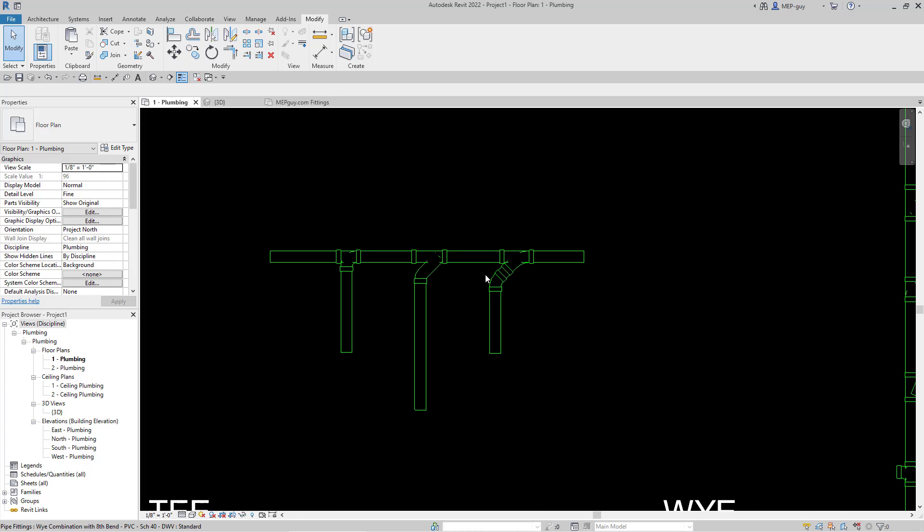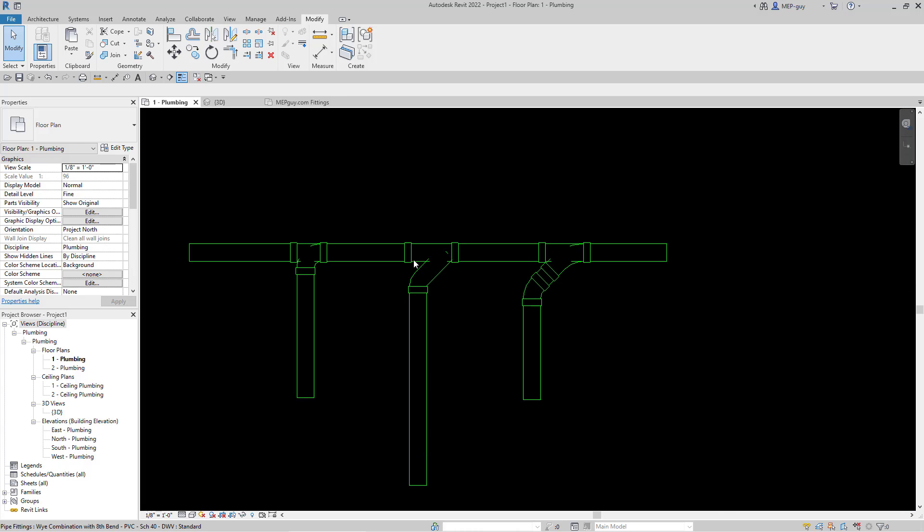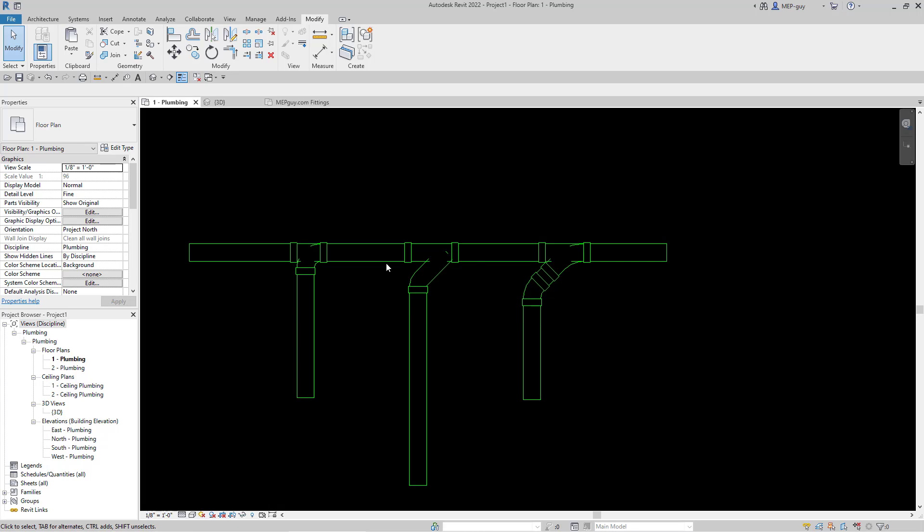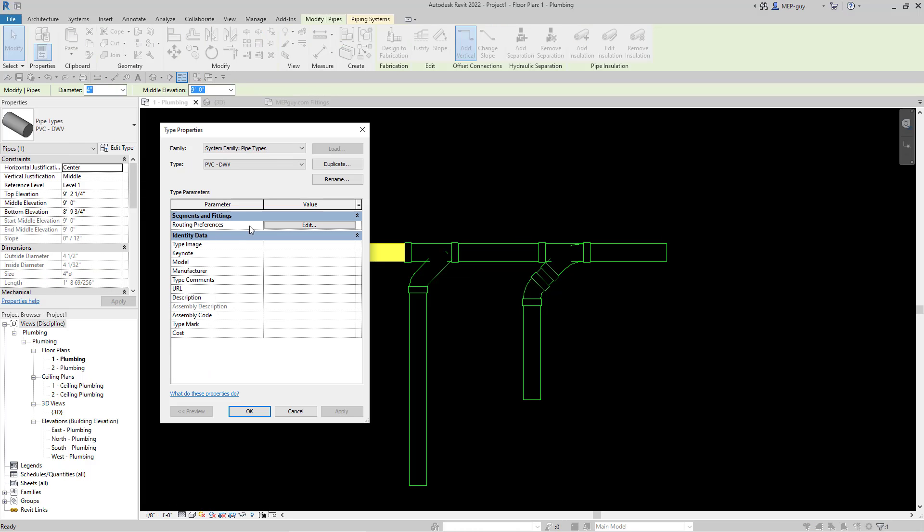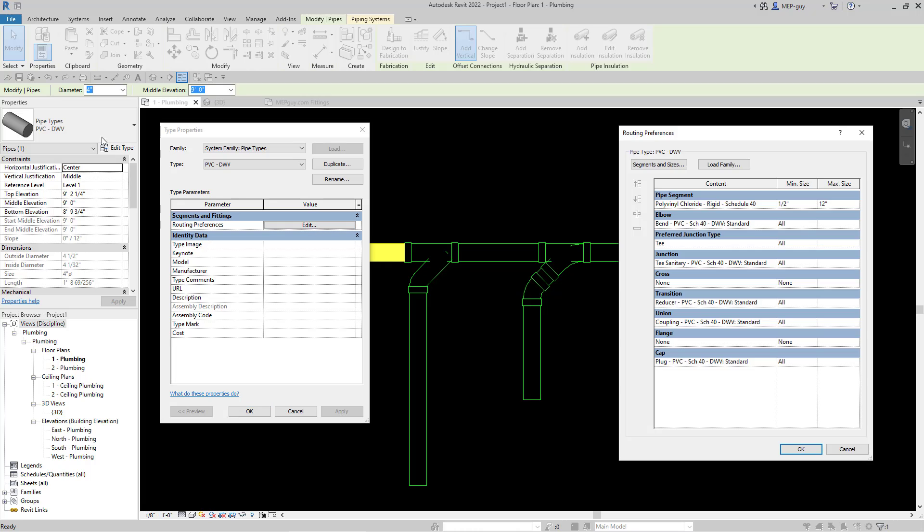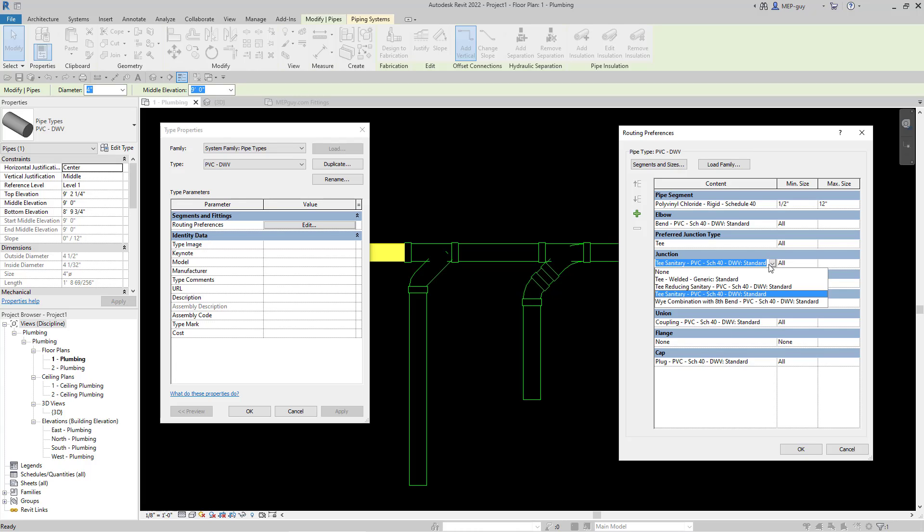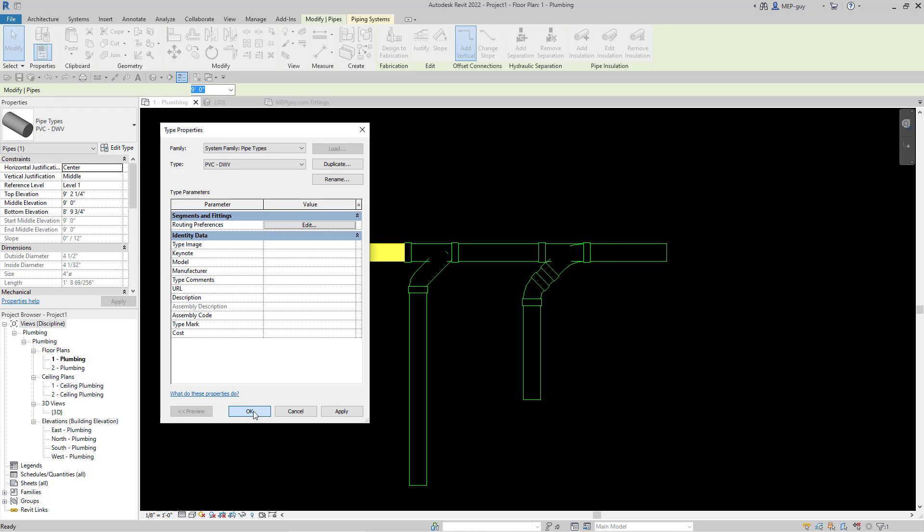So the first thing we have to do though, is we have to set our routing preferences. So anytime we T into this sanitary pipe, we get this special fitting right here, which is code compliant by the International Plumbing Code. So I'm going to click on my pipe, and I'm going to go to edit type. And then under routing preferences, I'm going to hit edit. And this is for my PVC type pipe. And right now you can see junction, my preferred junction is a T, which I'm going to leave. And then my junction type is this T sanitary, which we already said is not legal. So we're going to actually use this Y combination instead. And I'm going to hit OK, and hit OK right here.